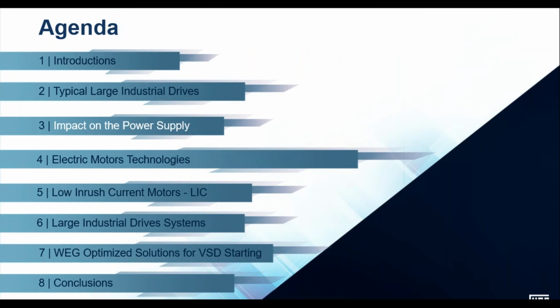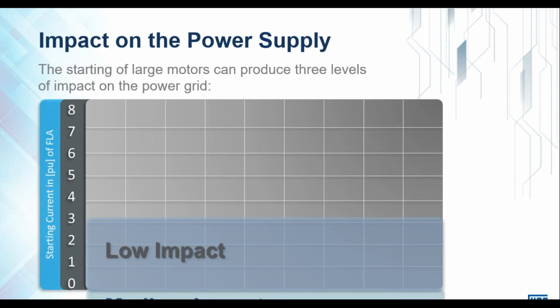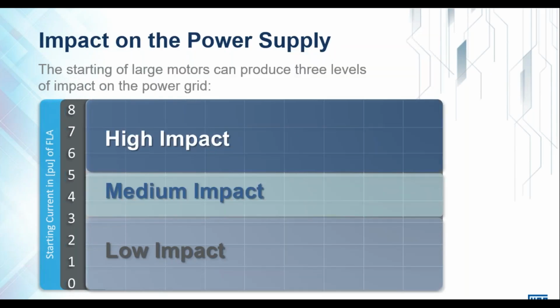Okay, so we've defined the different load conditions. Now we're going to classify the motor design in terms of its impact on the power supply. This will also be a very common theme to most people. We're just setting some classifications for ease of comparison later. So we define the starting of large motors in 3 levels of impact on the power grid. Remember, the impact on the power grid is affected by the starting current of the machine. In this case, we are defining low impact as 0 to 3 times the nominal current rating of the machine. 3 to 5 times is medium impact, and 5 to 8 times is high impact.